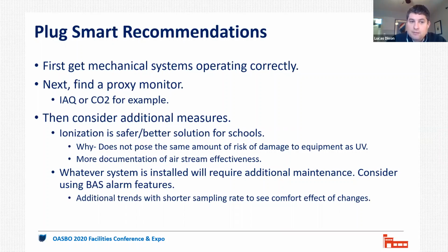In summary, our recommendation when looking at UV lighting and bipolar ionization is that first you have to make sure your mechanical systems are operating correctly. Are your air handlers and rooftop units operating properly? Have you already done everything you can to maximize the amount of outdoor air you're bringing in? The solution to pollution is dilution, as the saying goes. The first line of defense for COVID-19 is to bring in more outdoor air and exhaust more indoor air.